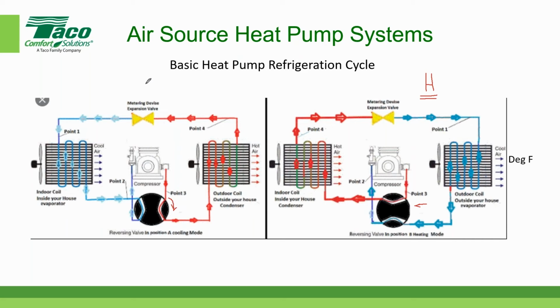They don't all look like this. They're usually a sliding valve. And this is a cooling unit. So we're cooling the inside. So there's the indoor coil. We're cooling the indoors. And here's heating, because we're heating the indoors. The refrigerant cycle is exactly the same, except we're changing the direction of the refrigerant, causing the indoor unit to go from a heating unit to a cooling unit. And that's how we can get heating or cooling out of the same device. Any questions about the reversing valve and how you can easily make a heat pump do either heating or cooling? Oh, it's clear as mud. Clear as mud. That's what we try to achieve here. We try to achieve mud level of quality here.